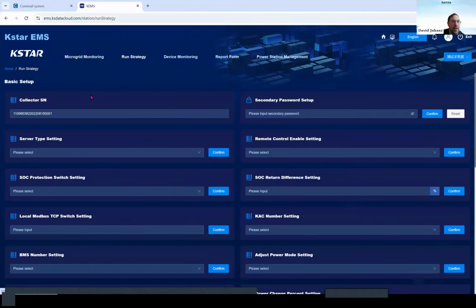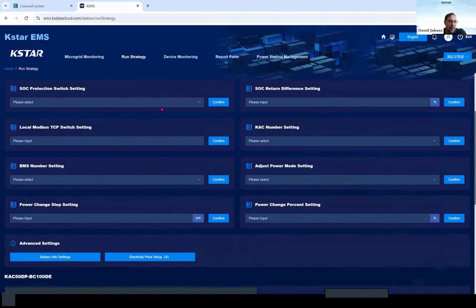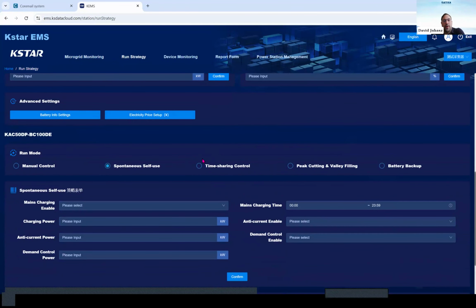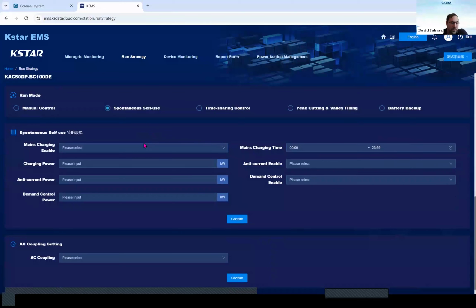If we go to the run strategy, we can set the different parameters here. It has a lot of things to adjust. If we scroll down, we can choose the operating mode. It has the manual control, mainly for troubleshooting or testing, or the third-party communication, reading and writing process. It has a spontaneous self-use, and this is sometimes the most common if we use PV for the system. It has the time sharing control, the peak and valley filling, and the battery backup. So for every operating mode, there are different things to set, and the best is to set every little detail of how we want to control the system.